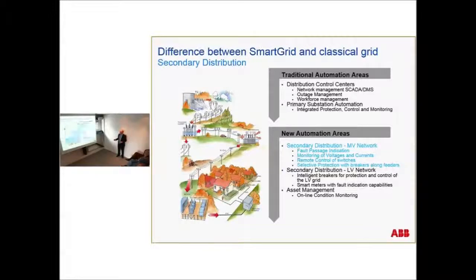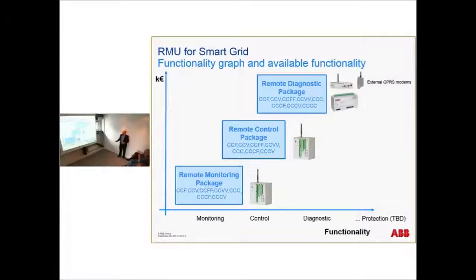This was too much text. I dropped that. So you see that the basic package from ABB on the ring main units, you can monitor voltage and you can monitor current. And then you have the second, that's the diagnostic. With all these smart small boxes, you can monitor: did I have a failure, an earth fault, which direction. And you can control it by this switch on, switch off.